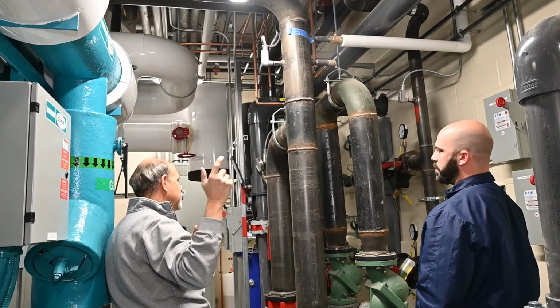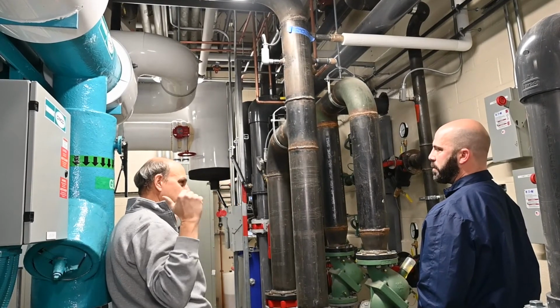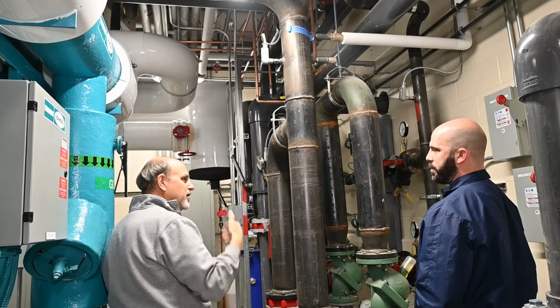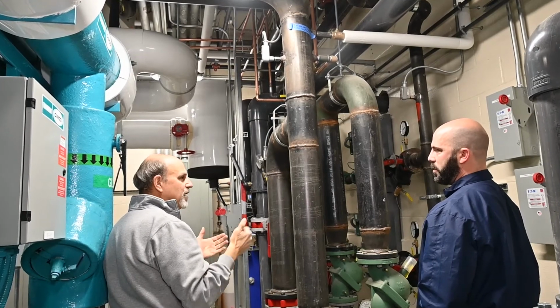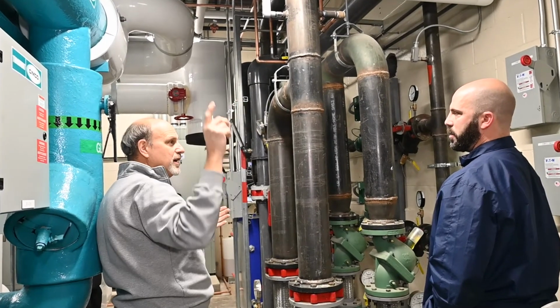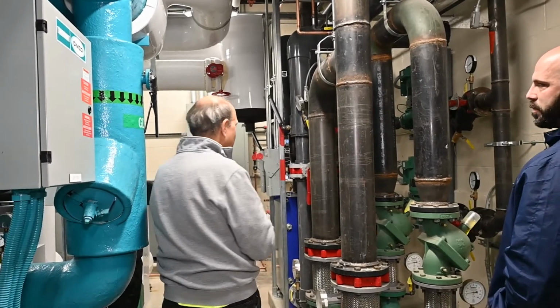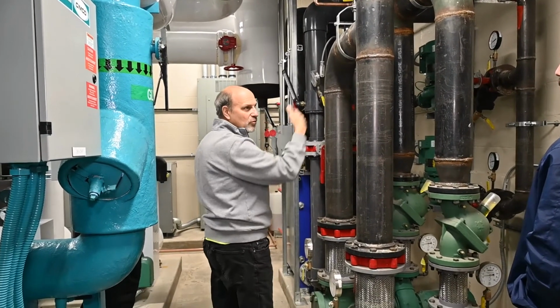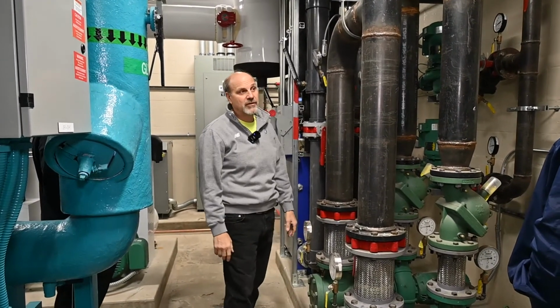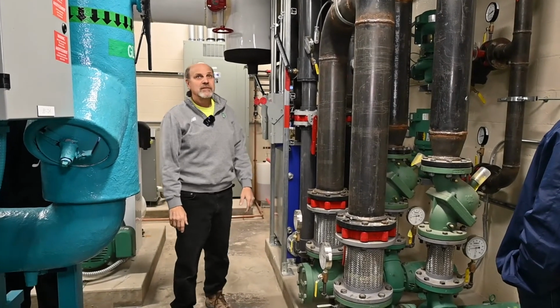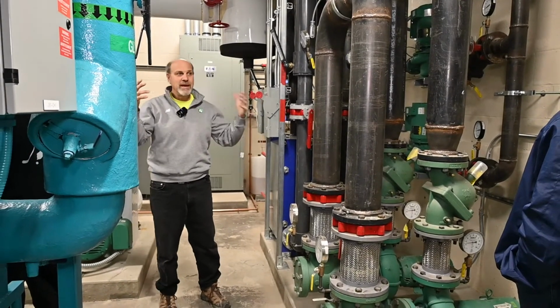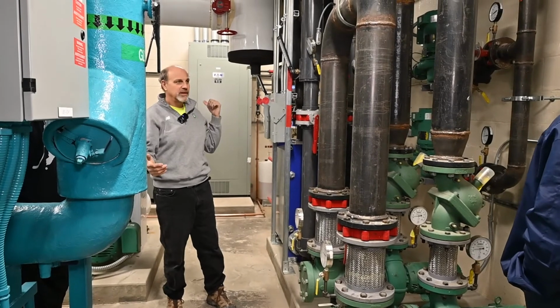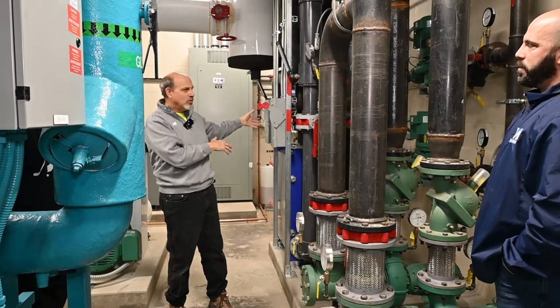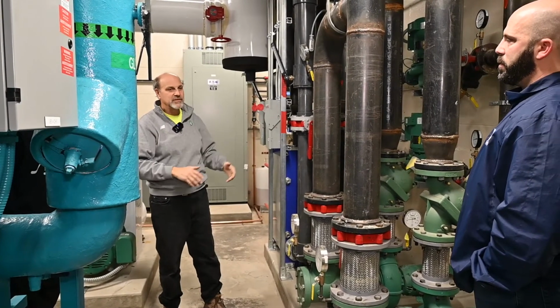So those systems are always going to run whenever the chillers run. So we're always going to be preheating the water. If the water's already preheated enough, it's just not going to reject any more heat. It's going to dump it to this heat exchanger, and this one is the workhorse that'll work to send it out to the cooling tower. Okay. So in a nutshell, that's the 2 main piping systems. Glycol loop for the rink bed, glycol loop for the warm floor, and your condenser system.